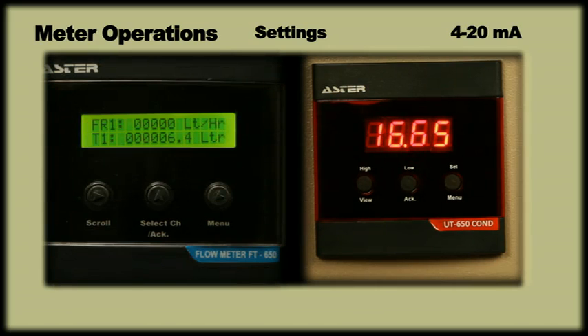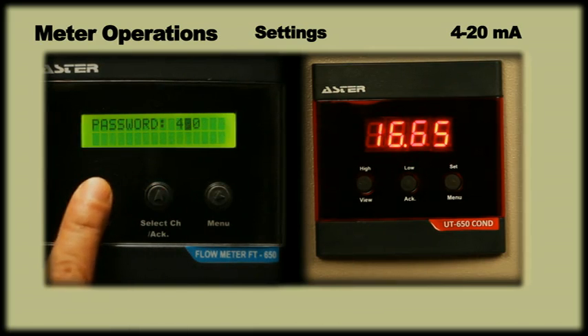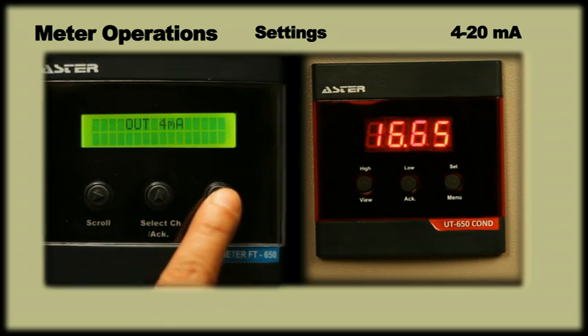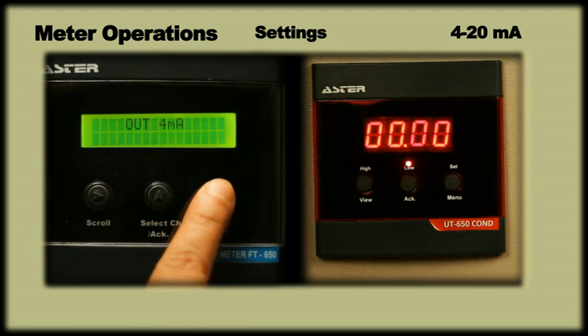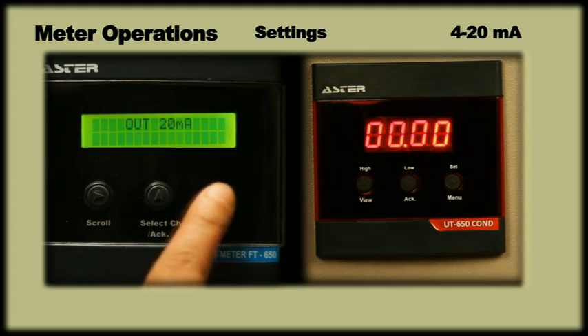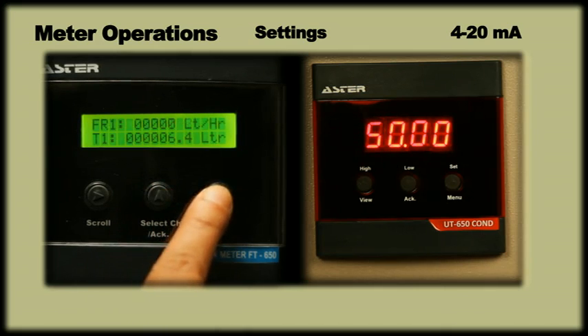To output standard 4 and 20 mA, enter password 420. Press menu key. Display will show 4 mA. Press menu key again to output 4 mA. Press select ch key. Display will show 20 mA. Press menu key to output 20 mA. Press menu key again to exit.